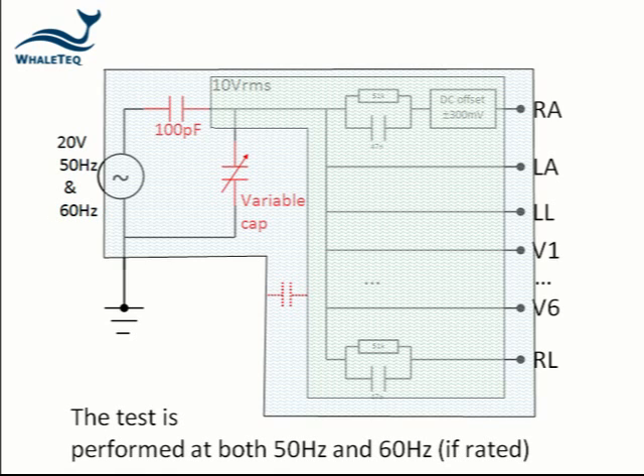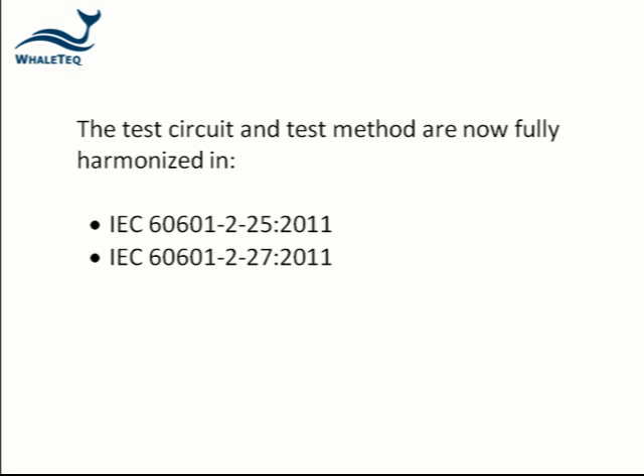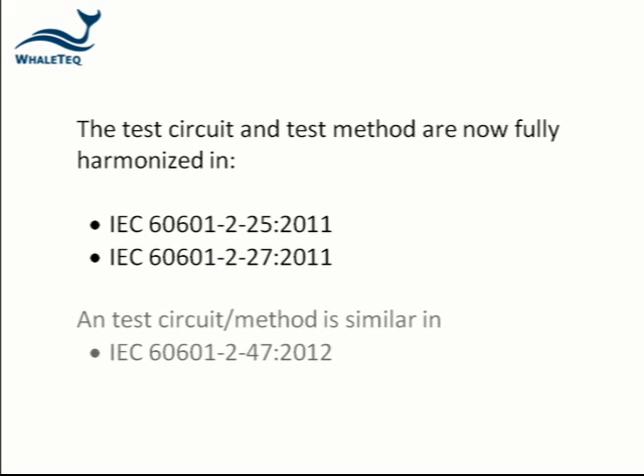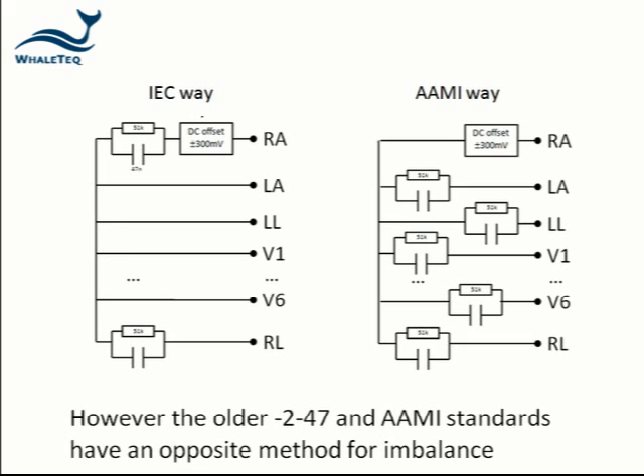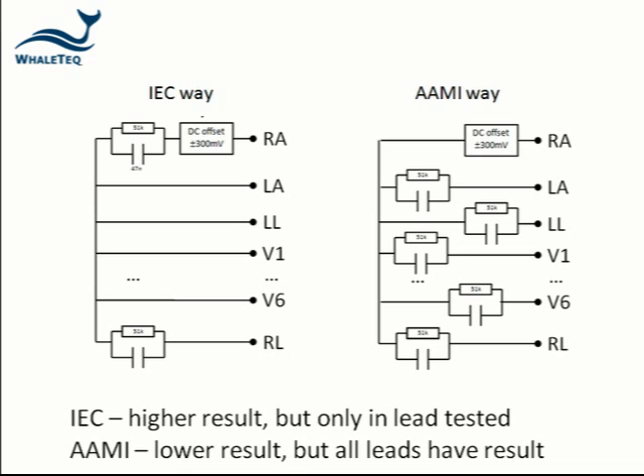The latest IEC standards require all mains frequencies to be tested, typically 50 and 60 Hz. The latest versions of 2-25 and 2-27 are fully harmonized for the test circuit and test method. Also, 2-47 has the same test method, except for the test voltage and frequency. However, the older version of 2-47 and the AAMI standards have an opposite approach to create the imbalance. The IEC version has the imbalance in one lead only, while the AAMI version has the impedance in each lead except one. The IEC version generally has higher results but only in the leads tested, while the AAMI version has lower results but in all leads.